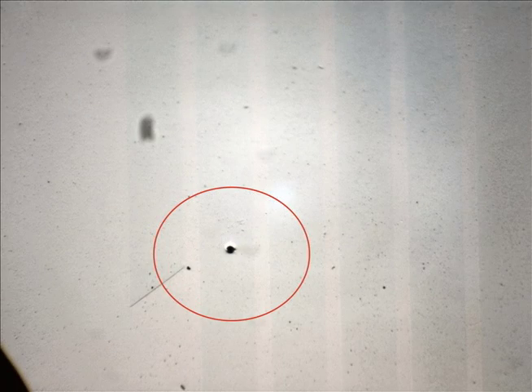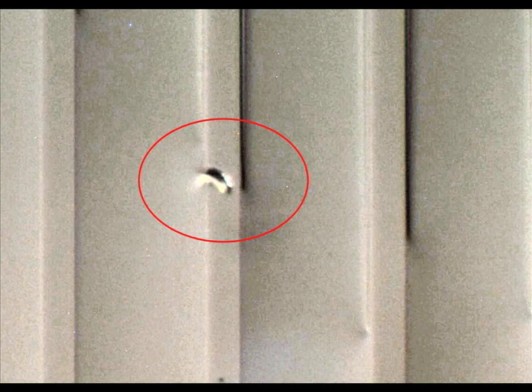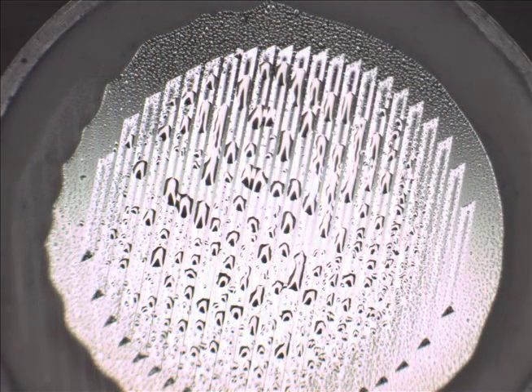Here are a number of photographs of damaged windows. Although the origin of the damage is unknown for most of them, the damage seen was catastrophic enough to warrant factory repair. Because of gentle handling procedures, most failures seem to occur from particle impacts or mechanical puncture.